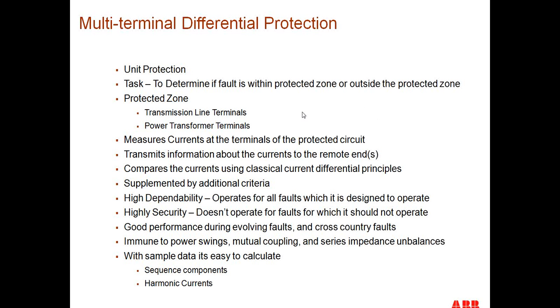The measured line, so as we were saying before, because we're sending sample data across the line, it's very easy to calculate the sequence components and harmonic components, which makes application of these relays to certain areas where they weren't applied before much easier, as we'll see in a little while.